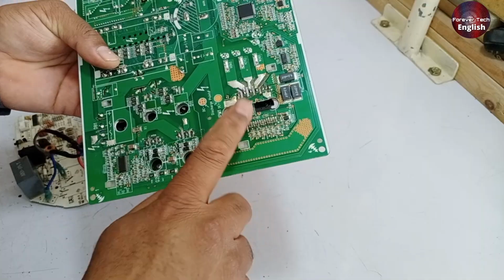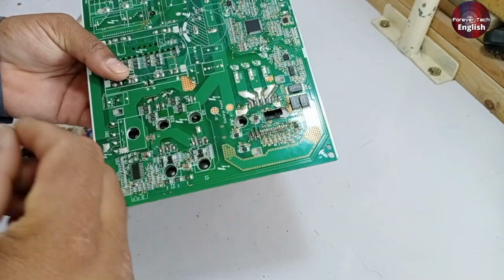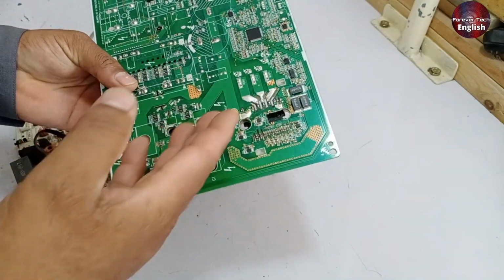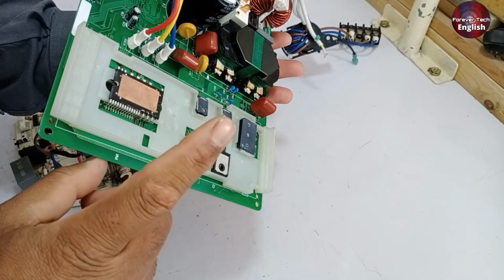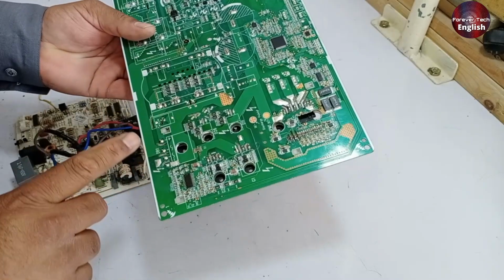To fix this, we replaced the entire IPM module, which resolved the issue, and now the compressor is running properly. Additionally, both diodes connected to the IPM were replaced because such faults can often damage the IGBTs as well.